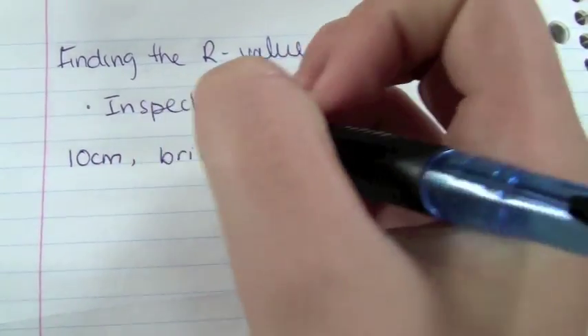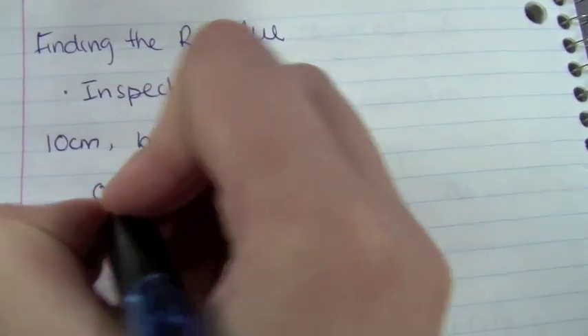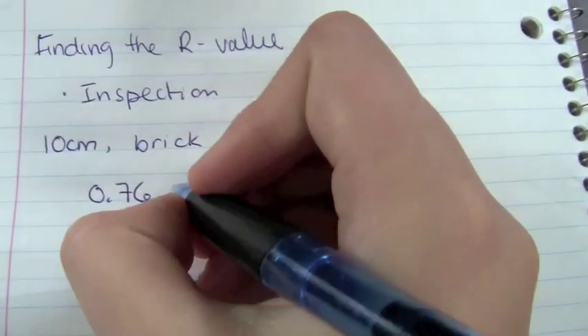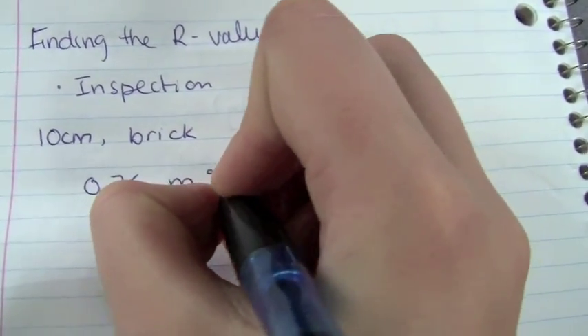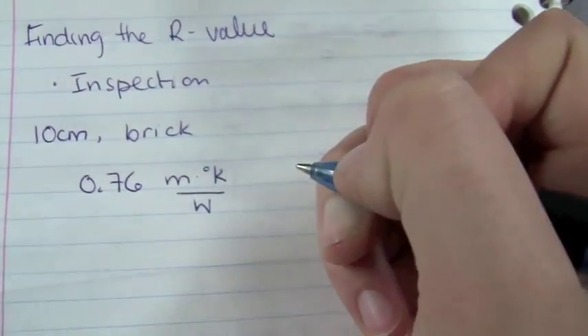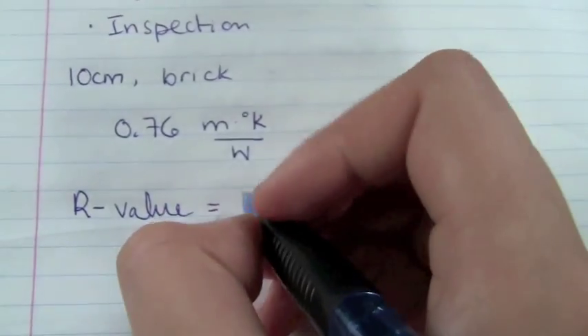Let's say in this case, I'm looking at a 10 cm thick wall that's made out of brick. The SI R value of brick is given as 0.76 meters times degrees Kelvin over watts. Now, in order to find the R value that I'm going to be using in future calculations, I simply need to multiply the thickness times this R value factor that I found.